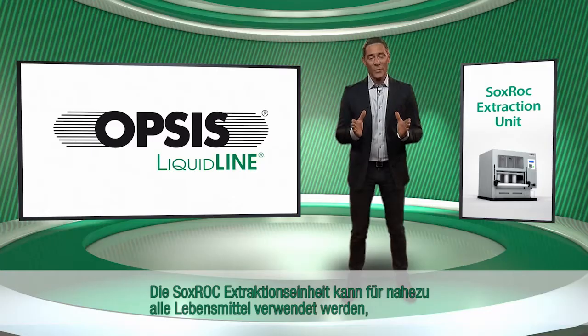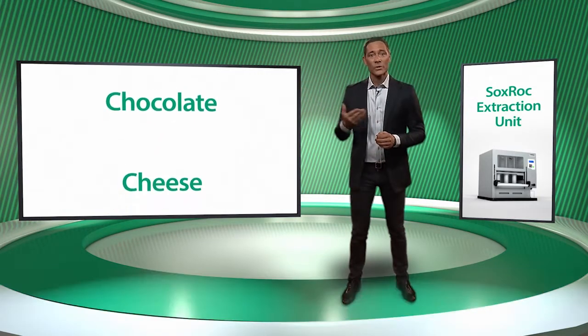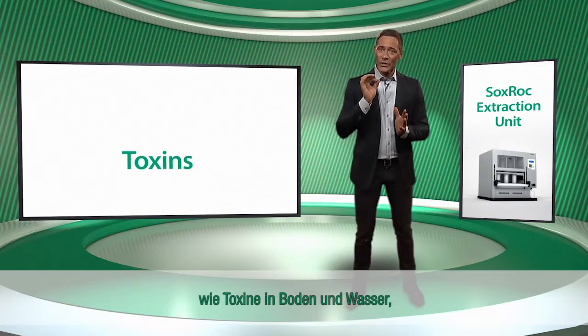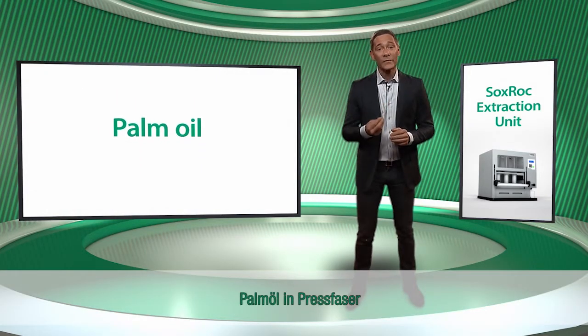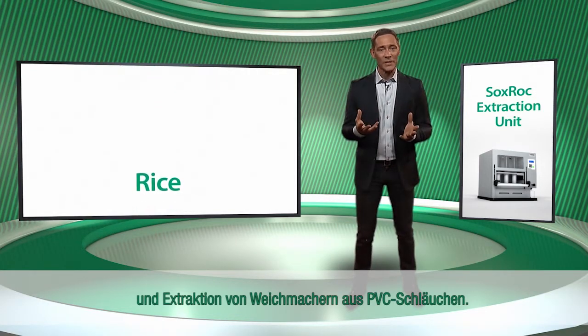The SoxRoc extraction unit can be used to analyse fat in most foods, such as chocolate, cheese, grain and meat. It can also be used for separation of other matters, such as toxins in soil and water, oil in slurry, palm oil in pressed fibre, and extraction of plasticizers from PVC tubing.